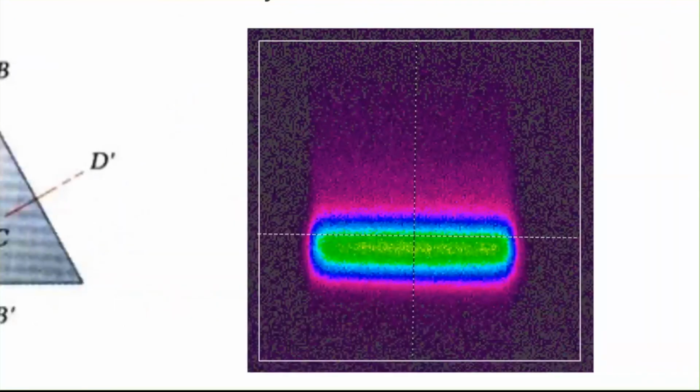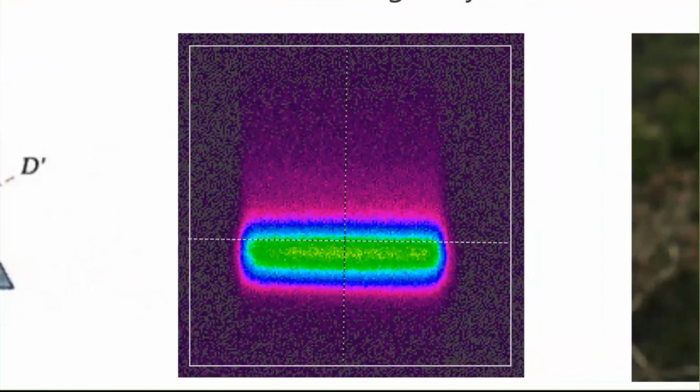When we're looking at a laser beam, we'll see different effects, such as this low-lying signal that sweeps up towards the top of this beam causes the centroid, which is the point where the dashed lines intersect. That is the cursor feature in Beam Gauge. You can see instead of being in the exact center of the green area, where one might expect it to be, all of this signal up towards the top of the beam pulls the centroid upward.